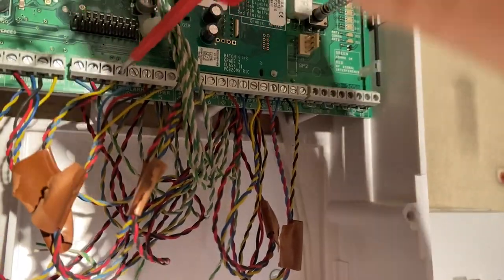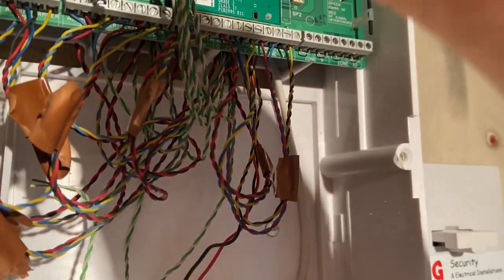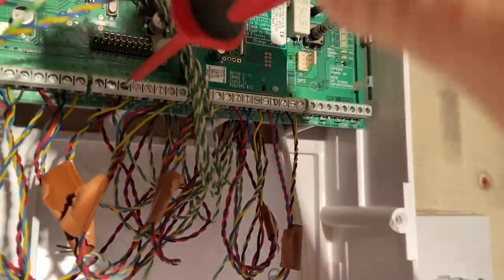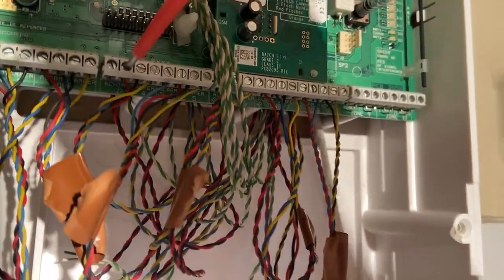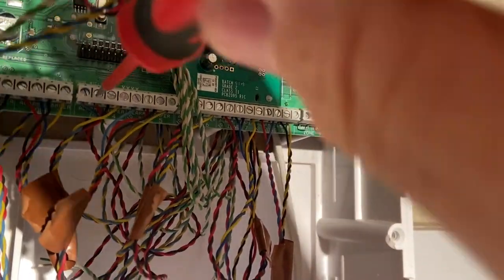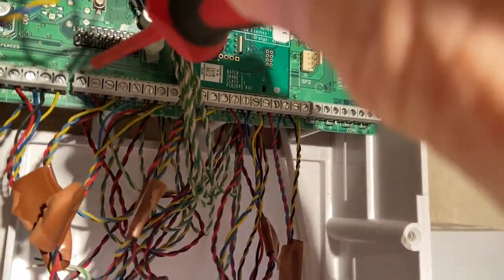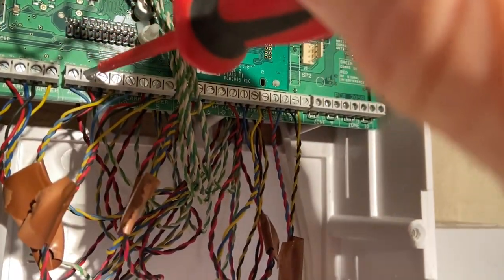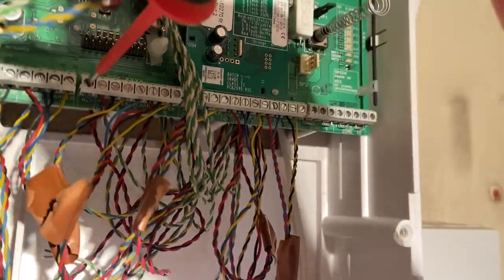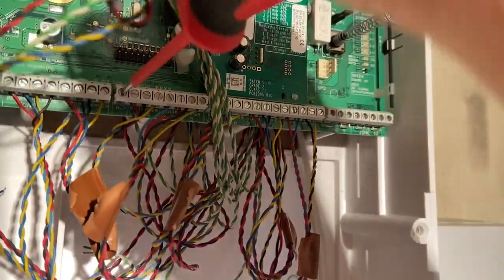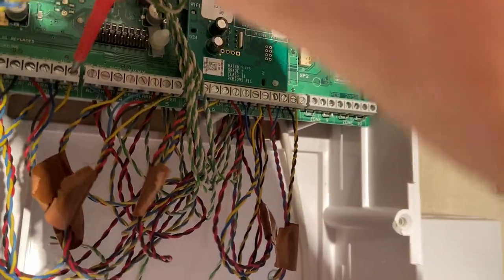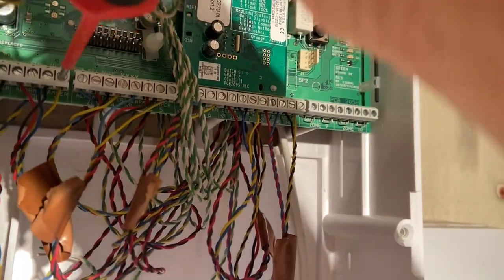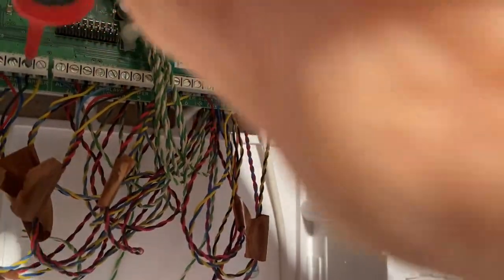The way you silence the Texecom bells is to drop the strobe down to zero volts and hit it six times quite quickly. So you drop it to zero volts six times and that will put the sounder into engineer mode.